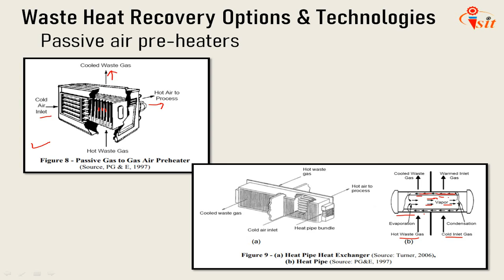The next type is the heat pipe heat exchanger. It consists of several pipes with sealed ends. Each pipe contains a capillary wick structure that facilitates movement of the working medium, here this working fluid, between the hot and cold ends. So hot waste gas, cold ends. Hot gases pass over one end of the heat pipe, causing the working fluid inside the pipe to evaporate. Pressure gradients along the pipe cause the hot vapor to move to the other end of the pipe. So here it is the arrow, vapor shown here, moving from left to right, where the vapor condenses and transfers heat to the cold gas. The condensate then cycles back to the hot side of the pipe via capillary action.